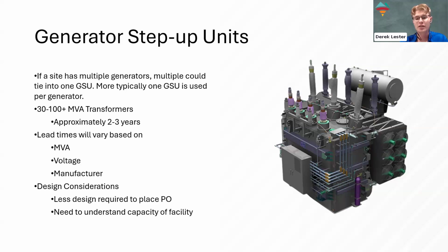For these geothermal projects, you're looking anywhere from 30 to 100 MVA, maybe even a little smaller. But for this range, you're looking at about 2 to 3 years lead time from PO to delivery to site. The things that impact this lead time are threefold. First, the MVA - the higher the MVA, the longer the lead time is likely to be, because a lot of facilities may not have the capability to build these larger transformers, so that market is thinner, leading to a farther out delivery timeline.